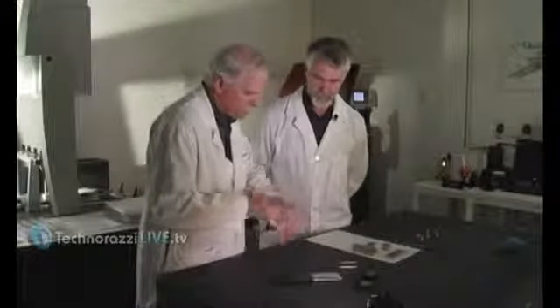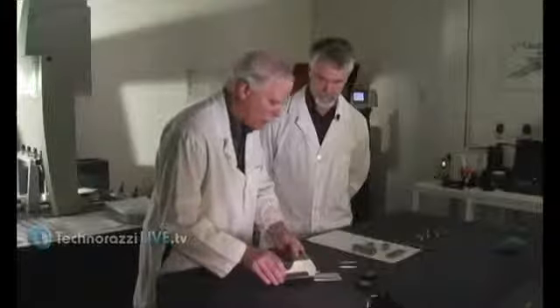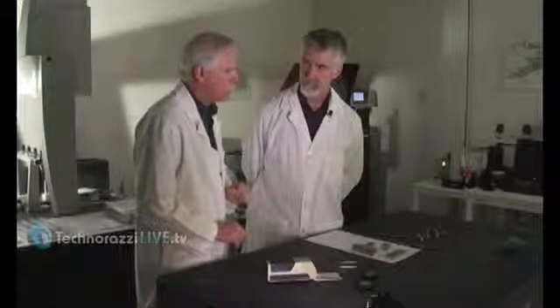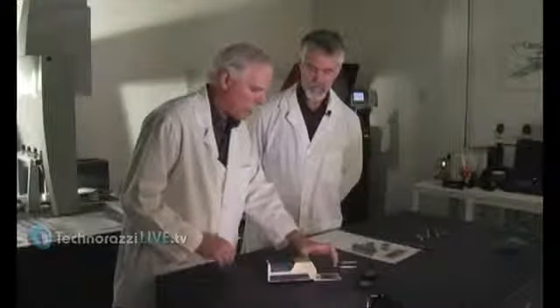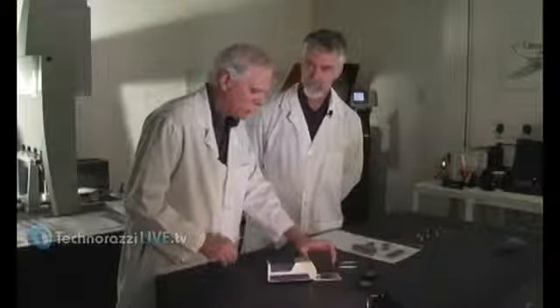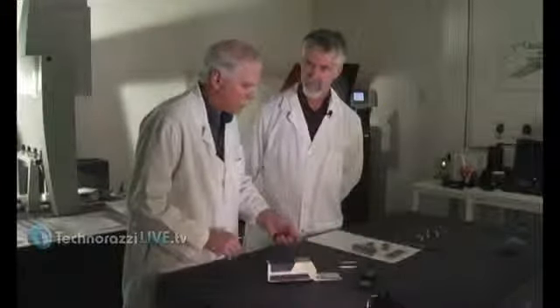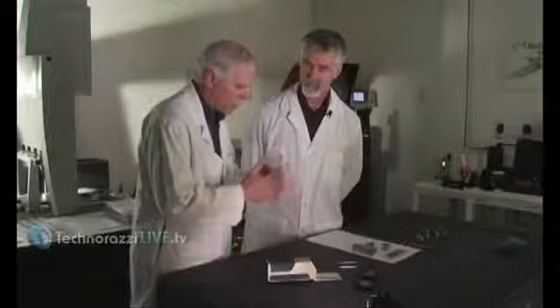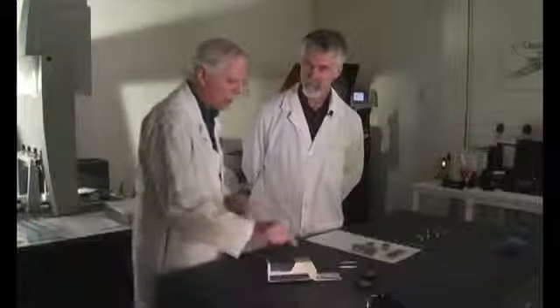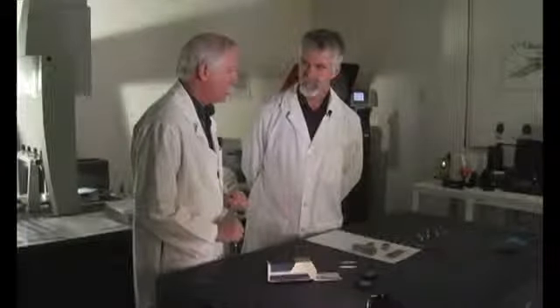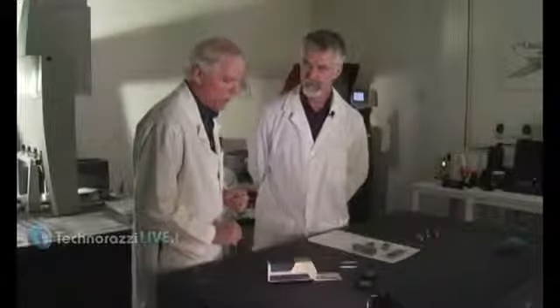Okay. A question we get asked a lot is, why do you calibrate up at 116, 118 when we're measuring something down in the range of 4 or 8? And the reason really comes to percentage of error. If you are a little bit off on this 118 or 116, as far as if there's any dirt, if there's any contaminant, if you're not entirely perpendicular, if there's any vibration during the measurement, it's easy to be off by 1 or 2 numbers, 1 or 2 millionths in this case.